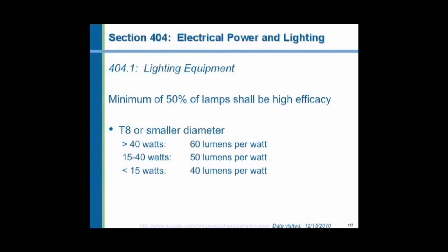The new code limitation of efficacy says that at 40 watts, 60 lumens, that's all you're allowed. If you were to have a magnetic ballast, you would be dropping that efficiency down. So you must use an electronic ballast in order to obtain this efficiency. The maximum output for fluorescent lamps at this time is about 100 lumens per watt, and that occurs in T5 lamps that are designated as high output, or HO. And light emitting diodes are approximately the same efficiency as fluorescent lights. The current light emitting diodes on the market, however, go up to about 120 lumens per watt.